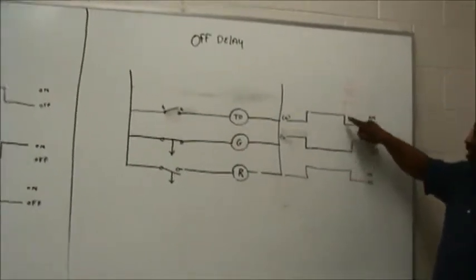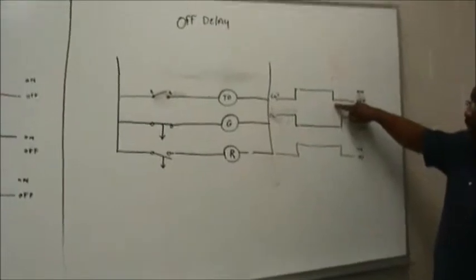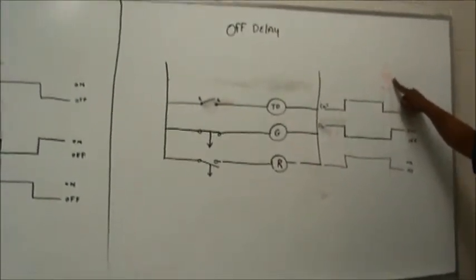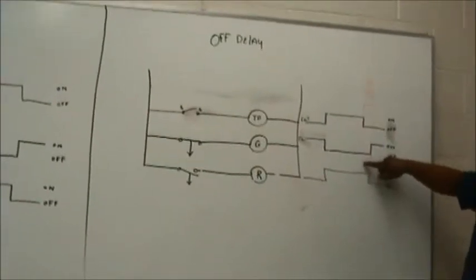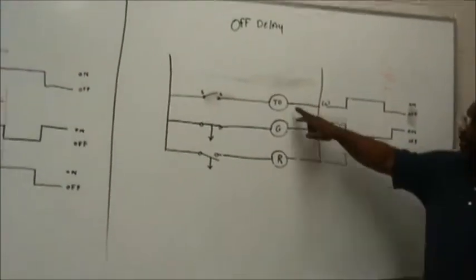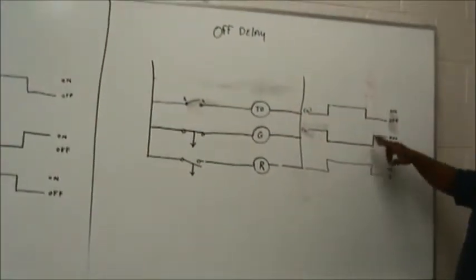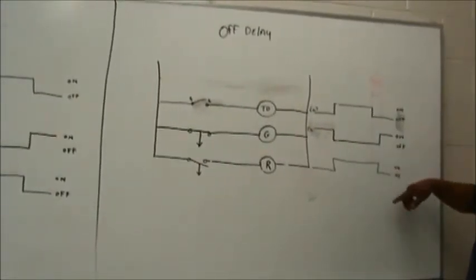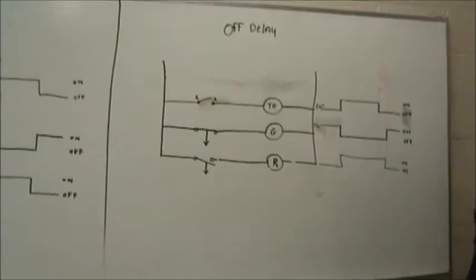Now, when I de-energize the coil of the timer, that's when the time starts counting, so that there will be a period, because the coil is no longer energized, there will be a period of time elapsed before the contacts go back to their original state.